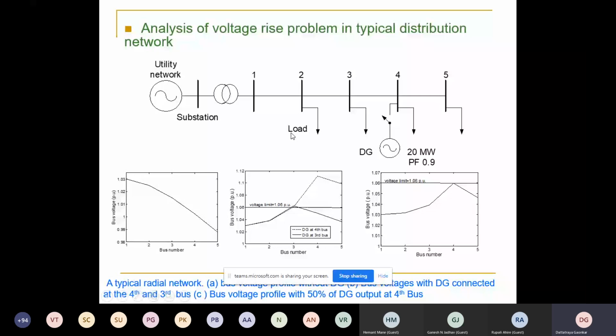Another important thing is connection point voltage becomes maximum as you go from the last customer to the substation, and voltage rise effect is less near the substation. Of course, it also gets influenced by multiple DG. So that is what you can see. Really, there is an issue, the voltage rise issue. This is an important issue in a smart grid.